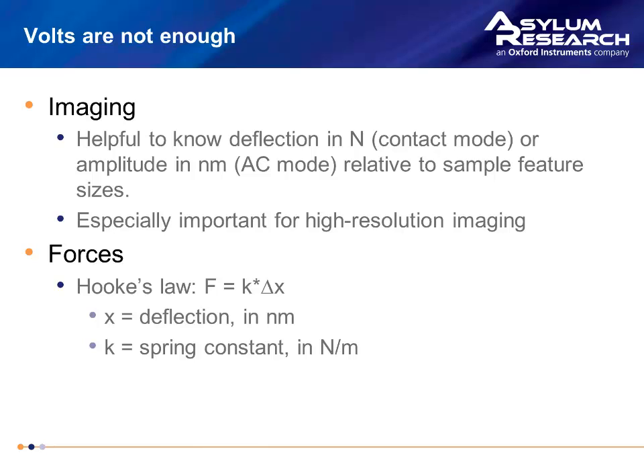And when it comes to force curve analysis, we usually use Hooke's law, which states that the force is equal to the extension of the spring in meters multiplied by the stiffness of the spring in newtons per meter. For both force measurements and for imaging, we really need to be able to convert this voltage that we've measured in the photodiode into something that's more meaningful to us.